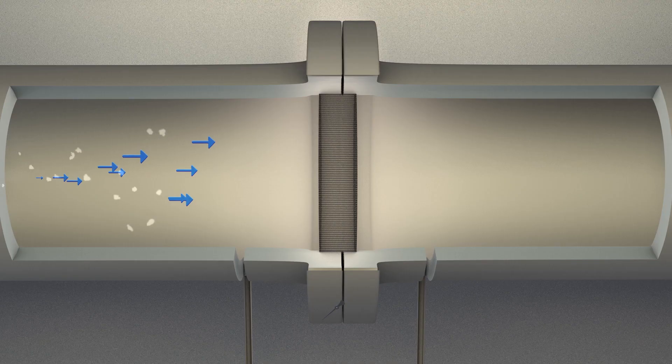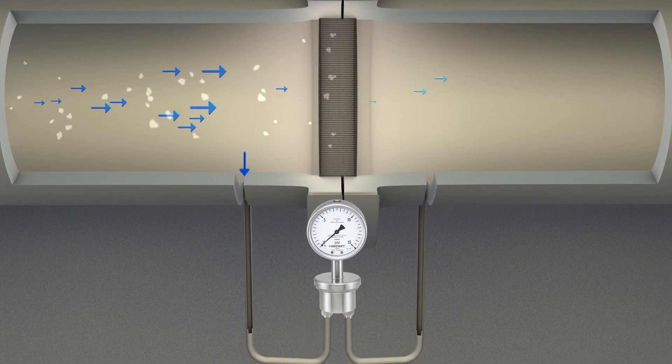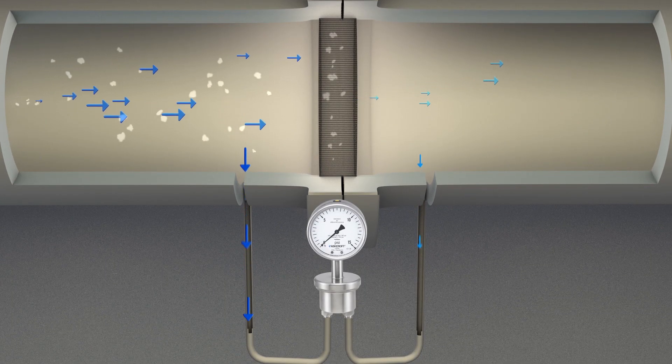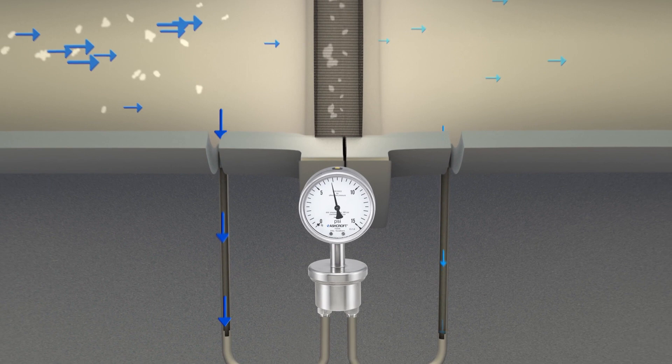So how can we measure the DP? Placing taps both before and after the filter, a differential pressure measuring instrument can be connected to detect the high side and low side pressures. The instrument will report the difference between the two sides.